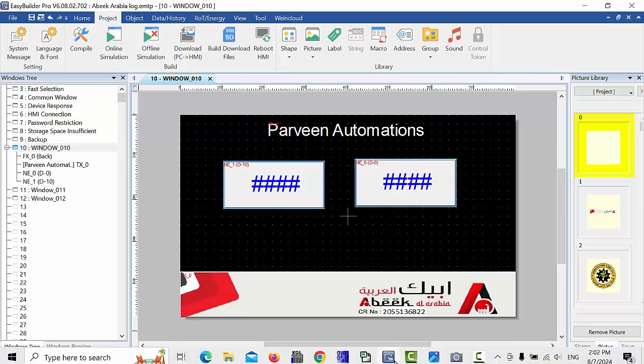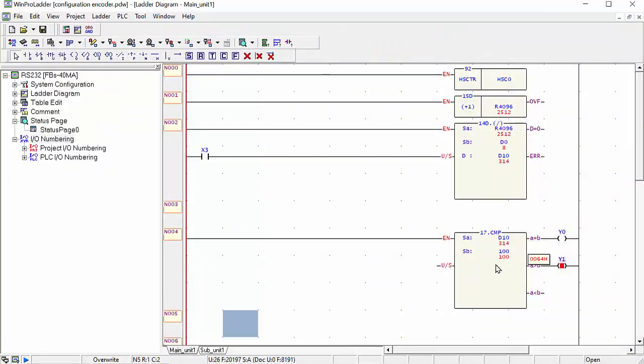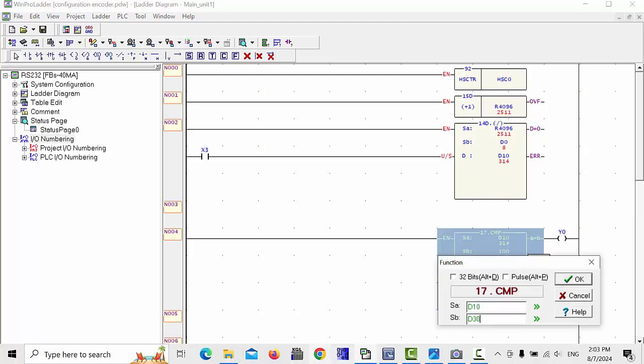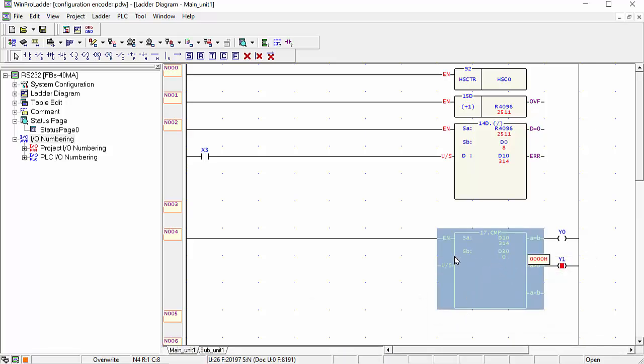Before downloading, let me explain D10 further. For example, if you want to stop your machine at 100 mm, when D10 equals 100 mm, Y0 will turn on or off — if on, your motor will stop. For flexibility, instead of hardcoding the stop value, it is better to use a data register. We will use D30 as the stop register, so wherever you want to stop, you write that value into D30.